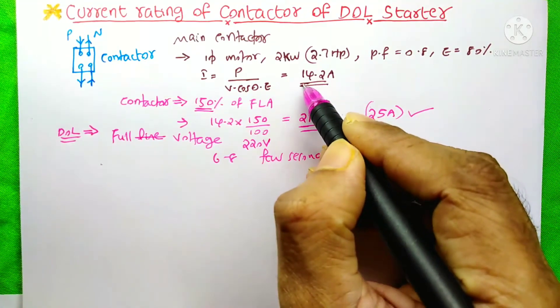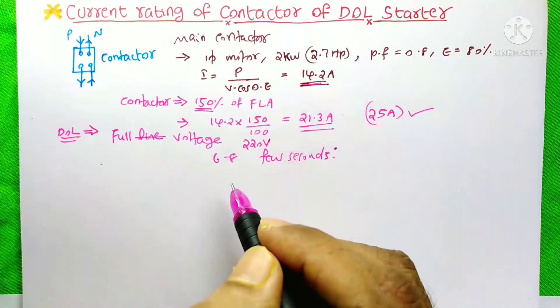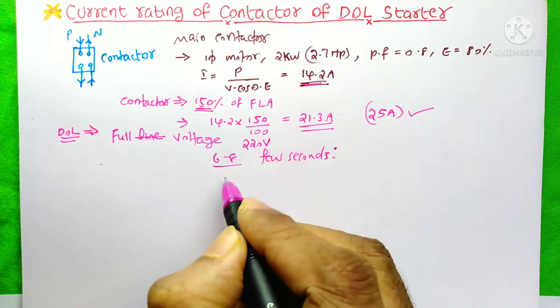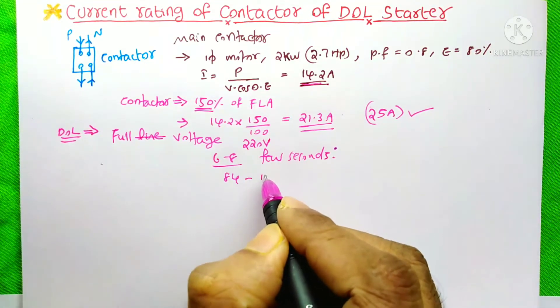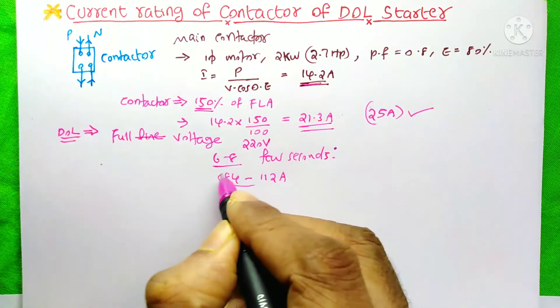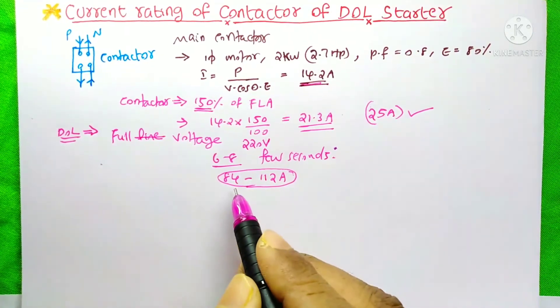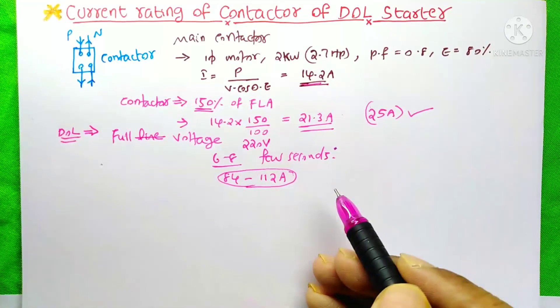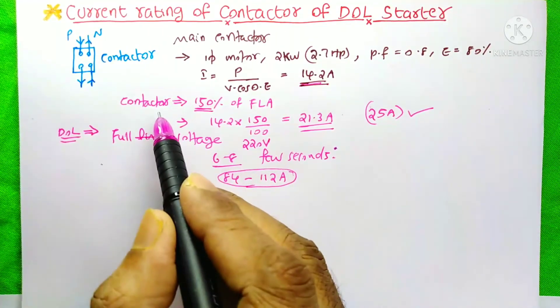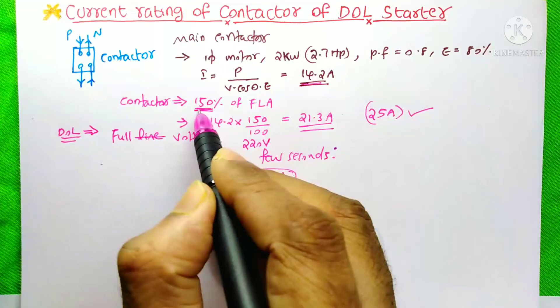In this case, our full load ampere is 14.2A. So its 6 to 8 times is 84 to 112A. It is something huge. So to withstand this high current for a few seconds, we calculate our contactor by taking 150%.